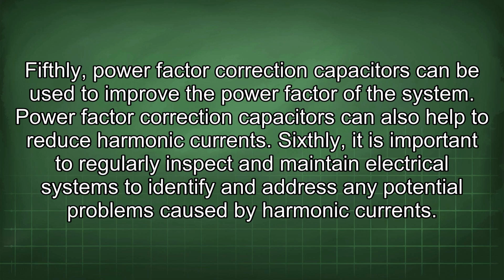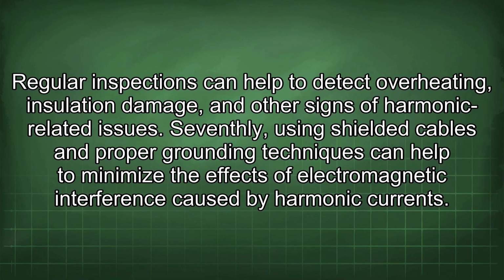Sixthly, it is important to regularly inspect and maintain electrical systems to identify and address any potential problems caused by harmonic currents. Regular inspections can help to detect overheating, insulation damage, and other signs of harmonic-related issues. Seventhly, using shielded cables and proper grounding techniques can help to minimize the effects of electromagnetic interference caused by harmonic currents.